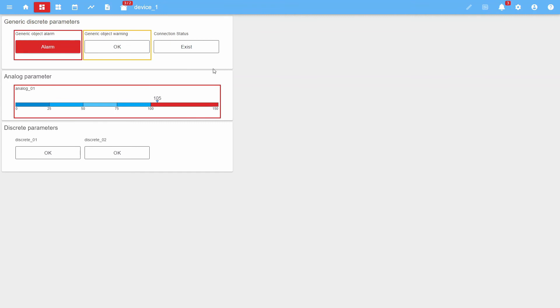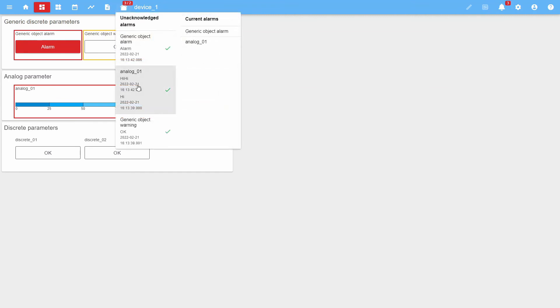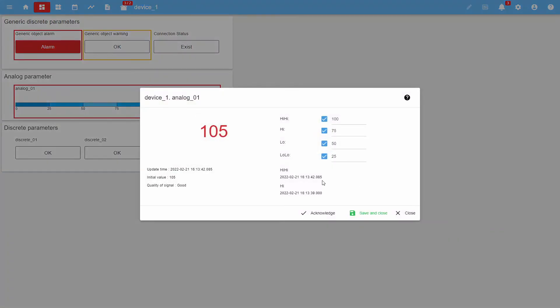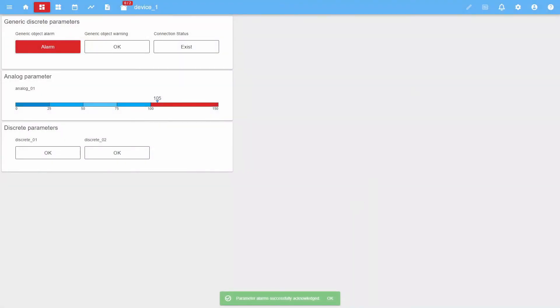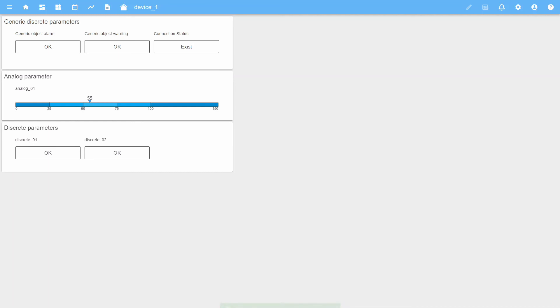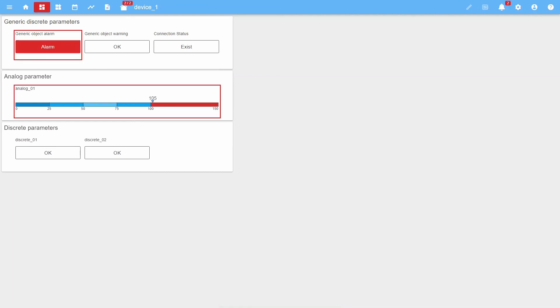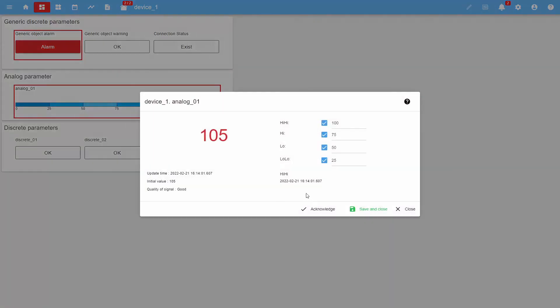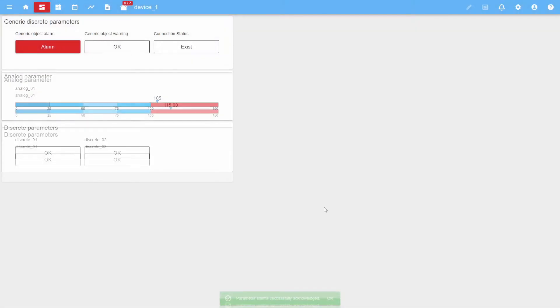For one of the parameters, two alarms were generated at once. This can be seen in the list of unacknowledged alarms and in a pop-up window when clicking on the widget. Let's acknowledge the alert and return the parameter value to the normal state. Now let's simulate the exit of the parameter value immediately beyond the alarm limit, bypassing the warning limit. In this case, only an alarm alert will be generated without a warning one. Let's acknowledge the alert and return the parameter value to the normal state.